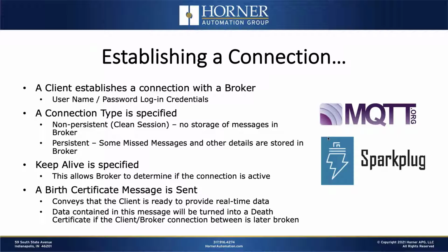Now, also on the client side, you're going to specify a keep alive, because the data that the client is publishing may not be changing very often. So you may just want to send periodically an indication to the broker that, hey, I'm doing well, the connection is active and healthy, I just don't have any new data to report. Because with MQTT, it's very common for a bunch of the topics to be reported on kind of an exception basis or a change of state type basis.